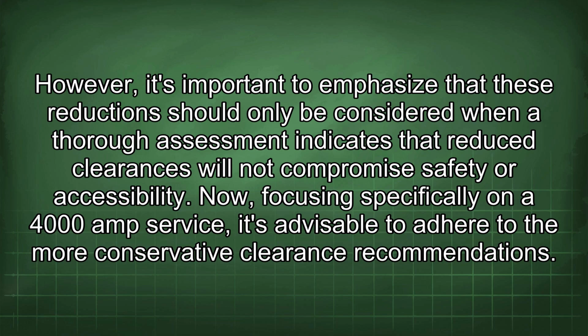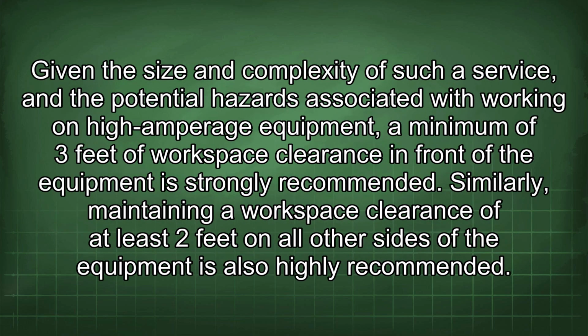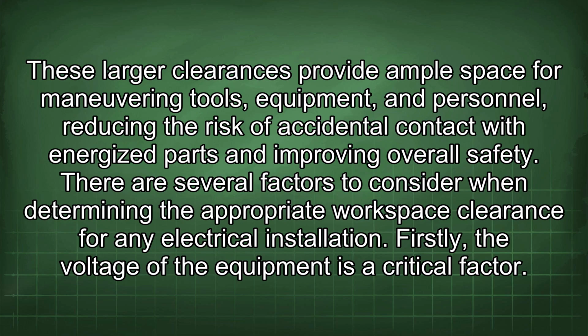Now, focusing specifically on a 4000 amp service, it's advisable to adhere to the more conservative clearance recommendations. Given the size and complexity of such a service, and the potential hazards associated with working on high amperage equipment, a minimum of 3 feet of workspace clearance in front of the equipment is strongly recommended. Similarly, maintaining a workspace clearance of at least 2 feet on all other sides of the equipment is also highly recommended. These larger clearances provide ample space for maneuvering tools, equipment, and personnel, reducing the risk of accidental contact with energized parts and improving overall safety.